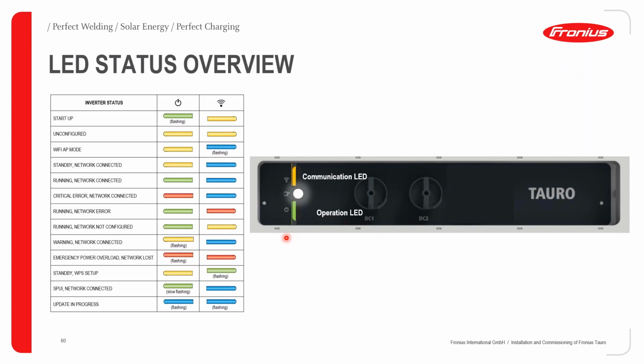So for this example, we can simply say that the inverter is on, that is, the DC and the AC cables are all connected, the inverter is powered and running, but it is in the process of being commissioned. So you have it indicating yellow, meaning that it is not yet configured. This can simply pass for this explanation. But just in case you have any of these other LEDs, you of course have this to help you explain what they all mean.